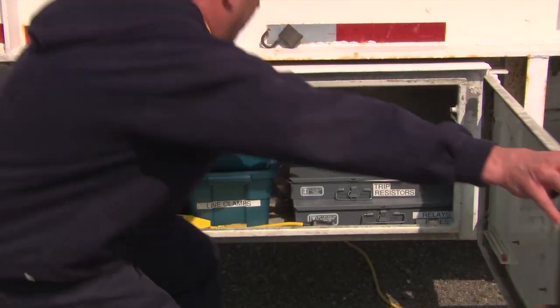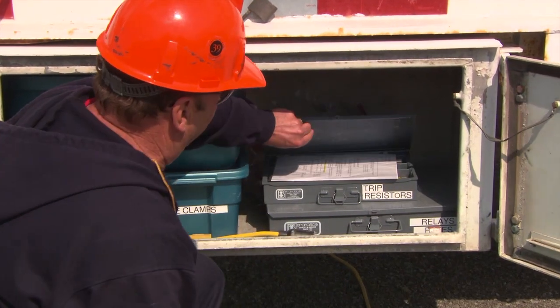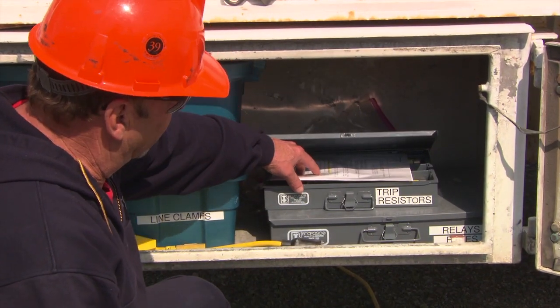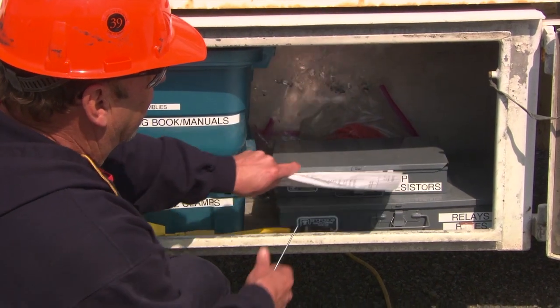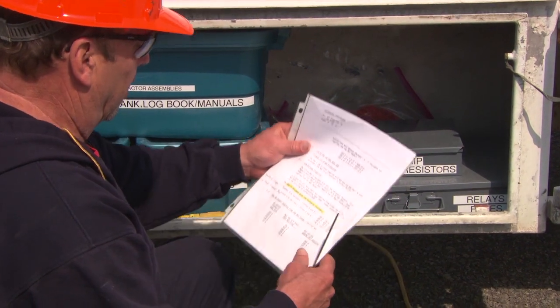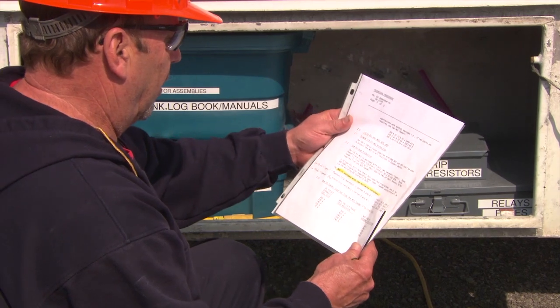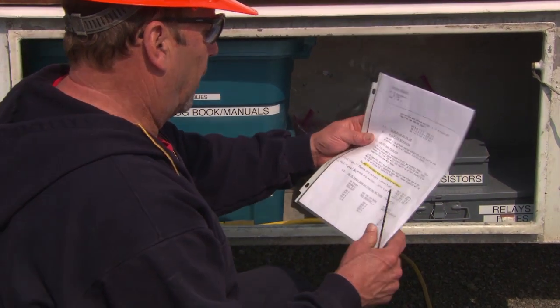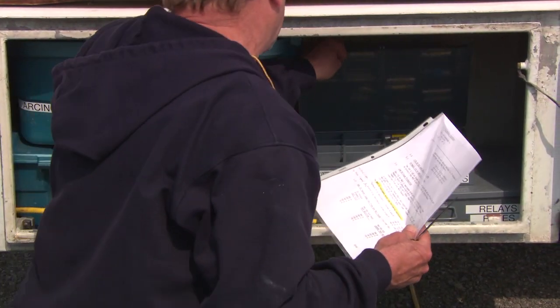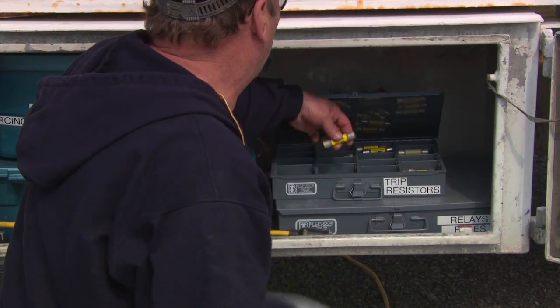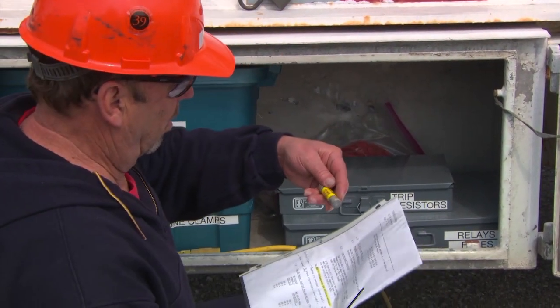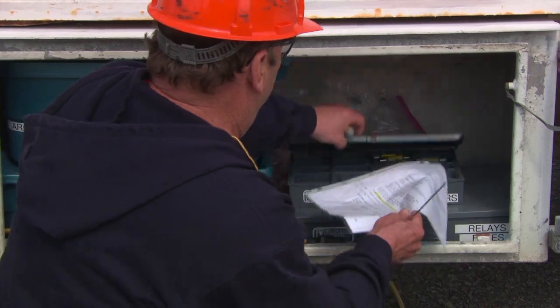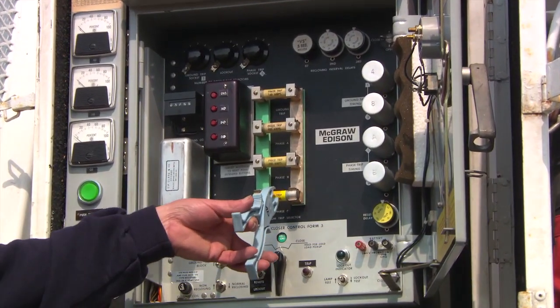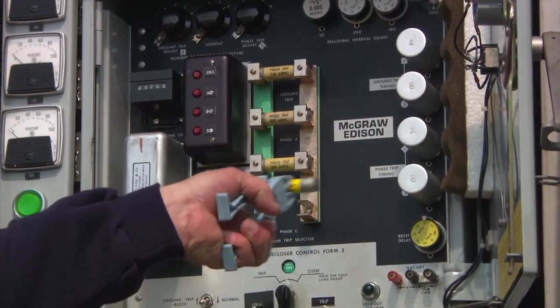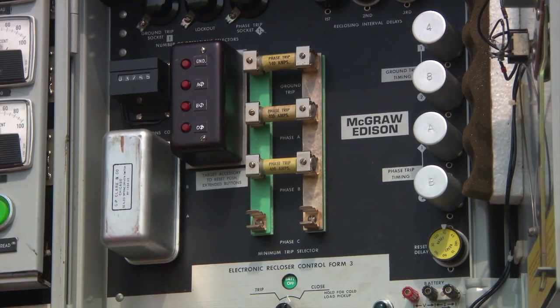Using Appendix C in SP 1610, select and install the appropriate phase trip and ground trip resistors to protect the low-voltage feeder circuits. These resistors will be found in the storage box on board the MUS. The minimum trip resistors establish the minimum trip current for the ground and each phase.